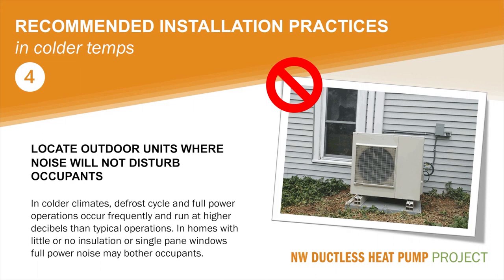The fourth practice is, locate outdoor units where noise will not disturb occupants. Consider this: in colder climates, defrost cycle and full power operations occur frequently. During these times, systems run at higher decibels than they do at typical operations. In homes with little or no insulation or single pane windows, full power operation may bother occupants, especially if the outdoor unit is located along a bedroom wall.